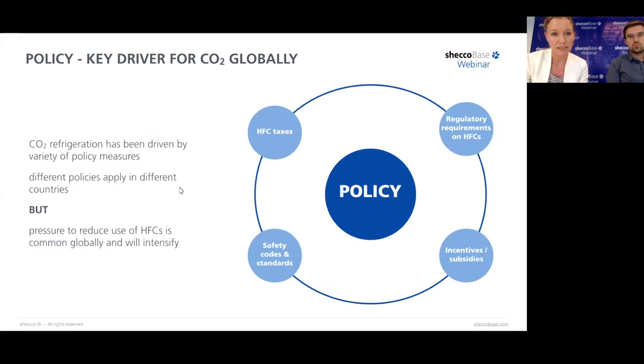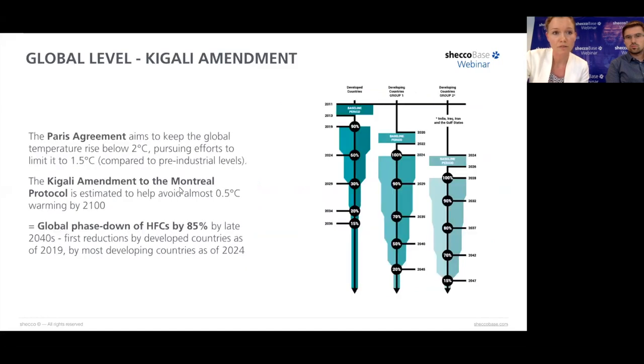When it comes to policy, this comes in different forms: requirements on HFCs, HFC taxes, initiatives, and subsidies. In essence, there are different policies in different parts of the world, but what is common globally is that there is increasing pressure to reduce the use of HFCs — and this pressure will only intensify. There has been an agreement among economies globally to reduce and phase down the use of HFCs under the Kigali Amendment to the Montreal Protocol, which will reduce the use of HFCs by 85% by the late 2040s.